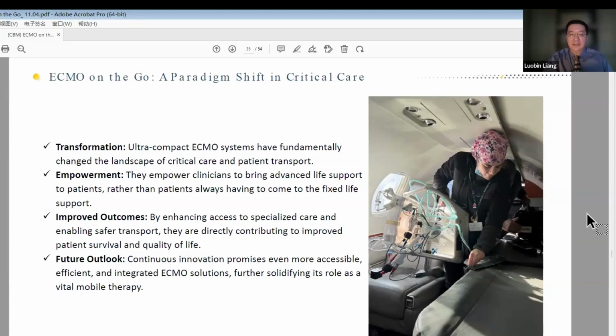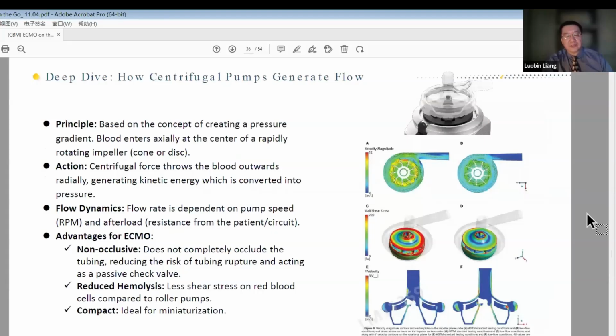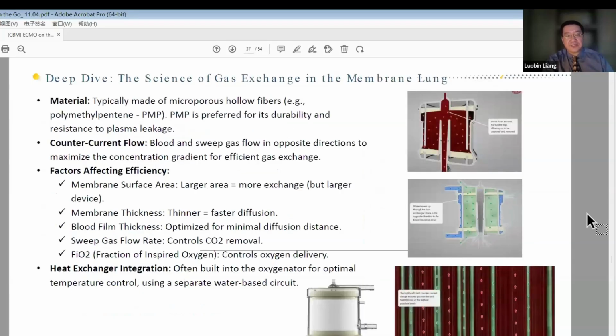Now some deep diving into these components when we consider making the ECMO system smaller, compact, or even ultra compact. Like I said before, the pump head. We want to design the pump head with better hemodynamics, to reduce hemolysis, making it smaller with less priming volume. The same goes for the oxygenator: better material for high efficiency gas transfer and integration of the heat exchanger, so we can minimize the whole system and at the same time provide highly efficient gas exchange.